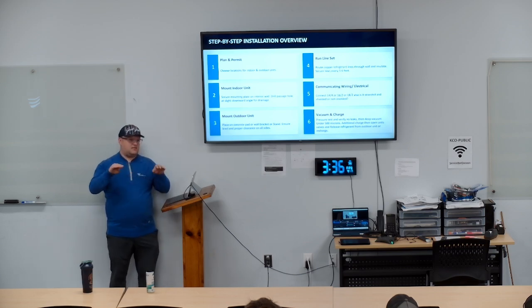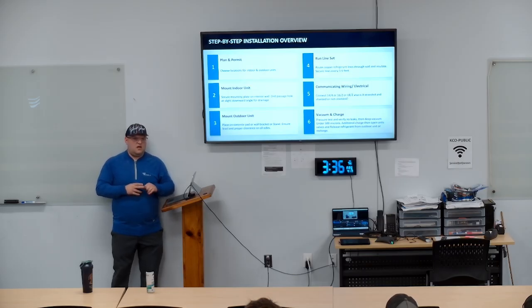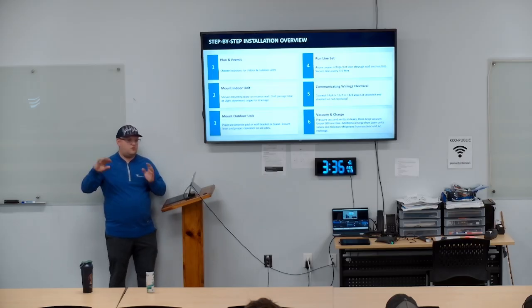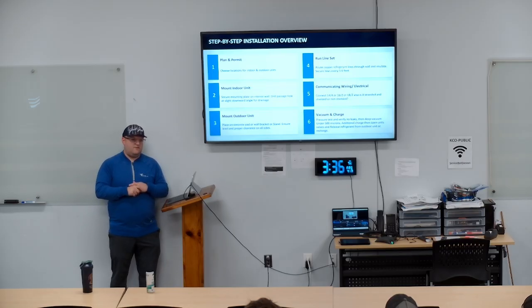And what it does is it eliminates interference from the communication wire. So nothing can come in between that wire. Okay. We ran for a while. We were saying, just run shield. It's cool. We'll have the shield if there's an issue. We don't have to use it.